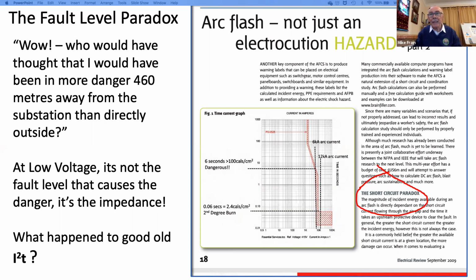And if you have a look on the right-hand side, I first came across that and named it the short circuit paradox back in 2009, I think it is that, in the Electrical Review, where I wrote an article there, the short circuit paradox. And the understanding is that it might seem blasphemous to a power engineer, but at low voltage, fault level can actually be your friend. And rapid disconnection of dangerous arcing faults can be the order of the day to protect workers.